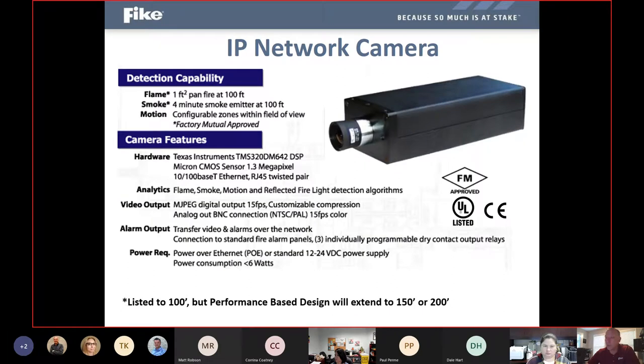The cameras that we still use today were actually first developed back in the early 2000s. You can tell just by the look of them there. They're not even a high definition camera. It's a standard definition camera with relatively low resolution and frame rates. And we're constantly working to improve this technology, and we have a high definition, much sleeker and smaller unit ready for release here shortly. But this one's listings and performance still are in accordance with what they need to be to meet the intents of all the codes as a smoke and fire detection system. So we do continue to use it here today.